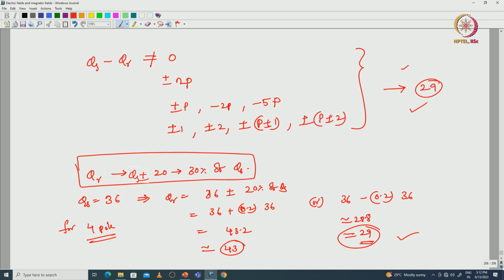And the other way is to skew the rotor. Whatever number of rotor slots we select, skewing the rotor will minimize the crawling, cogging, synchronous cusps, noise and vibrations and other effects. So, in this way we can find the number of rotor slots.